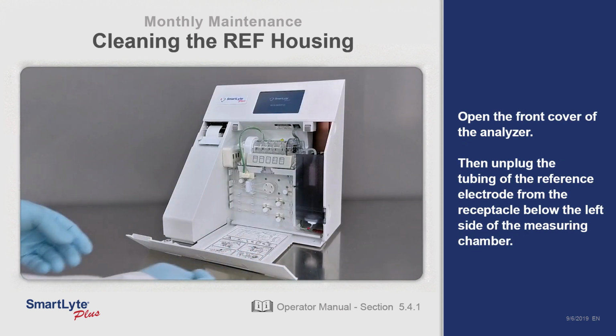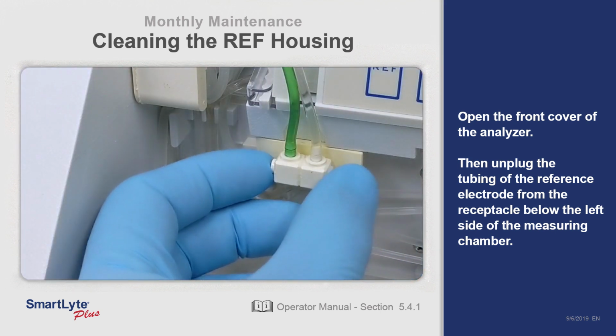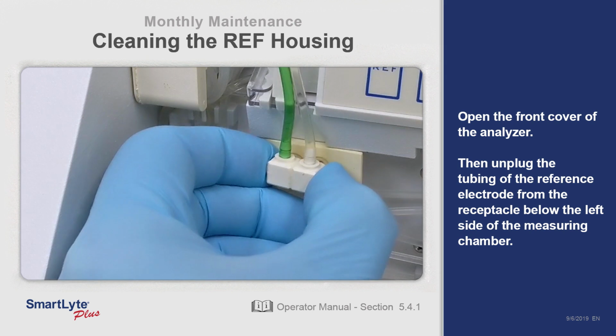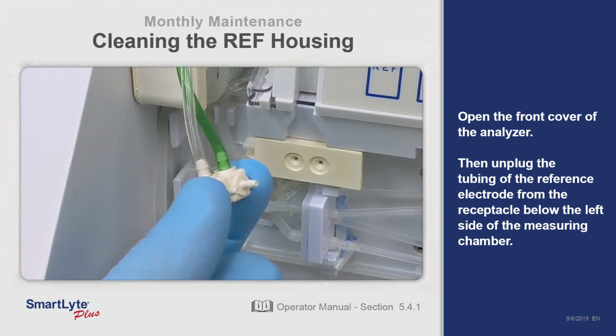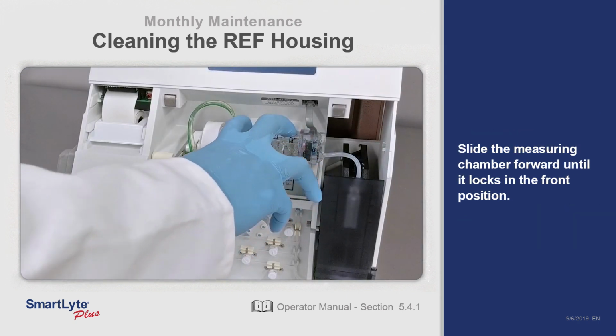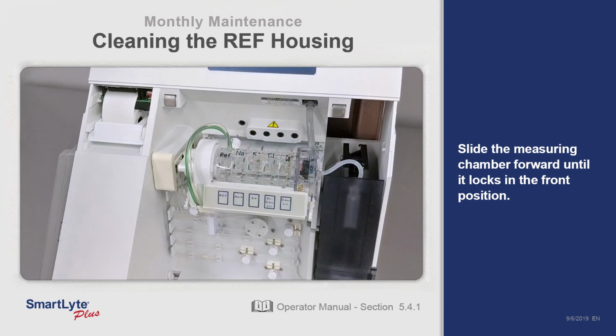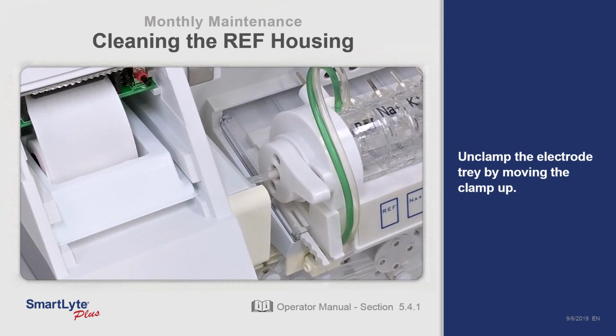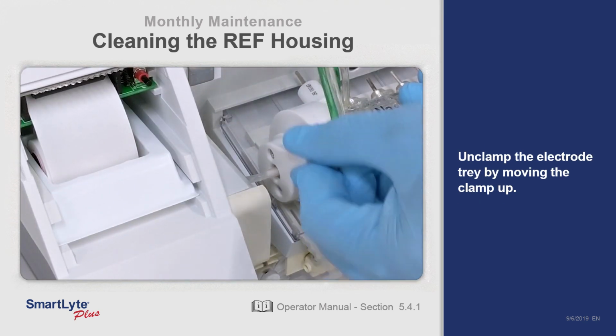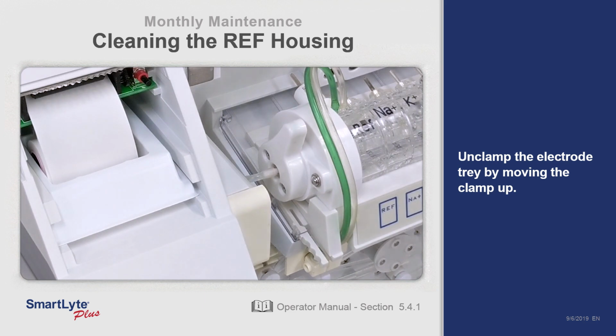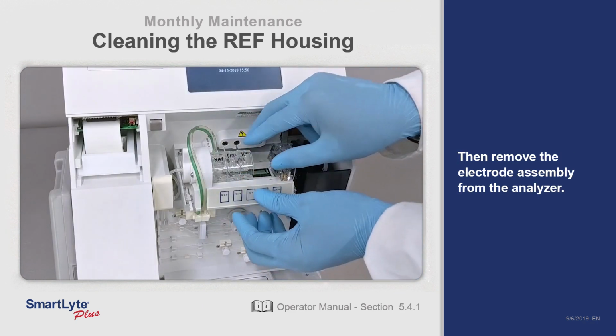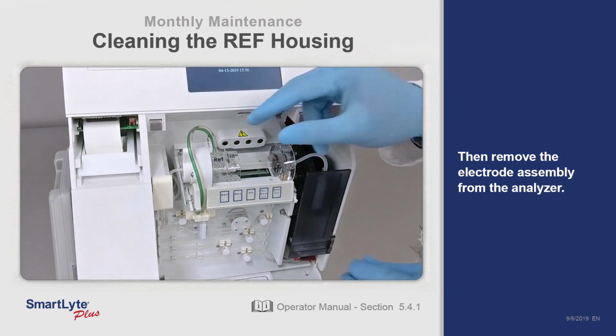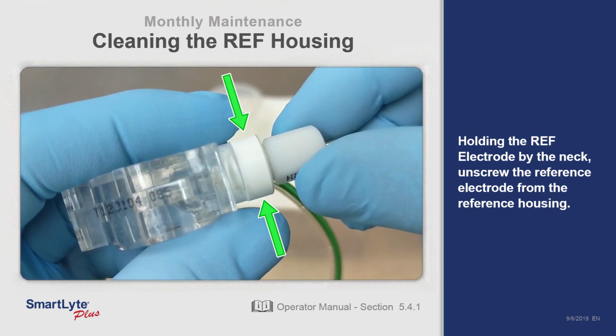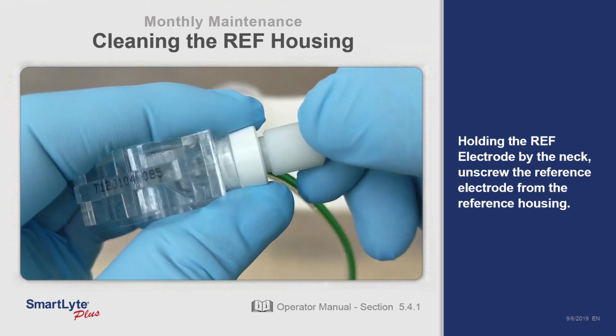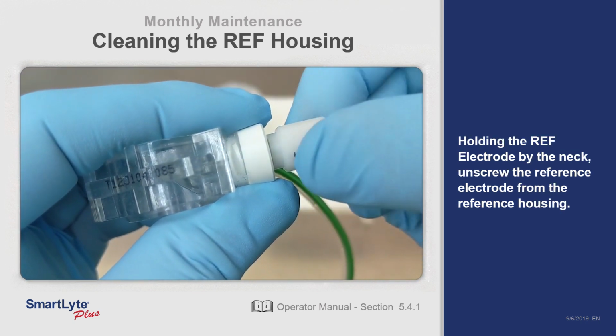Open the front cover of the analyzer. Then unplug the tubing of the reference electrode from the receptacle below the left side of the measuring chamber. Slide the measuring chamber forward until it locks in the front position. Unclamp the electrode tray by moving the clamp up. Then, remove the electrode assembly from the analyzer. Holding the reference electrode by the neck, unscrew the reference electrode from the reference housing.